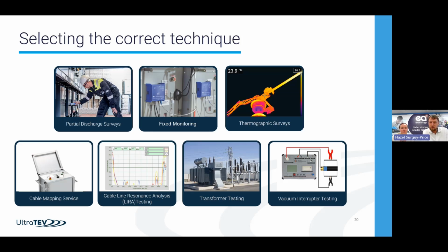Again, identifying issues. There are full transformer test sets where you can energize or take the transformer offline and test the insulation of the transformer. And complementary to this is very much the vacuum interrupter testing. So vacuum bottles are really common on the network now. A lot of them are reaching their design life. And how do you know that vacuum is still good? There are a couple of very simple techniques for taking measurements on them while they're in service and proving that the vacuum is still intact.